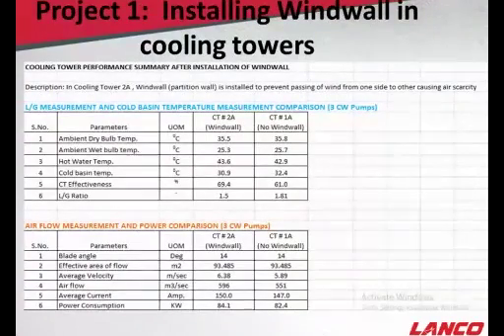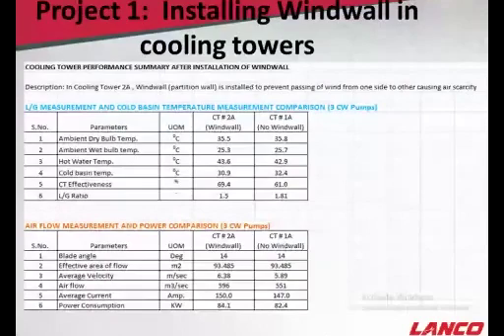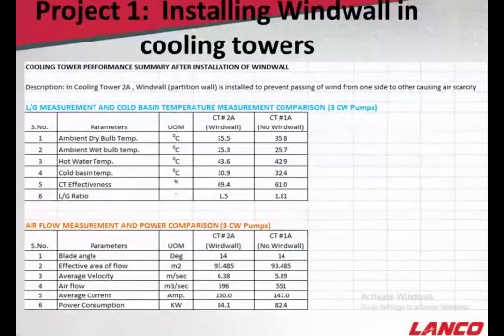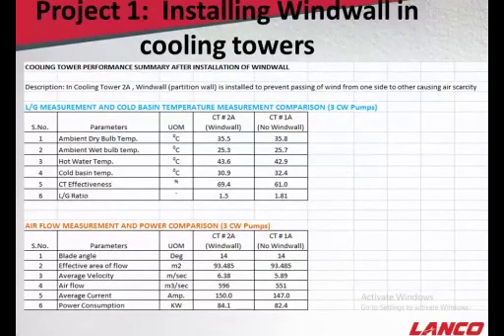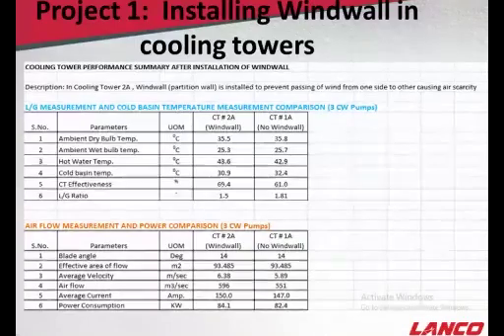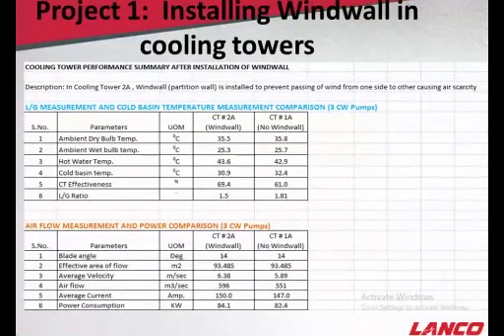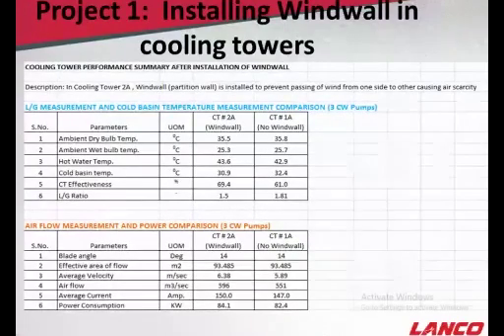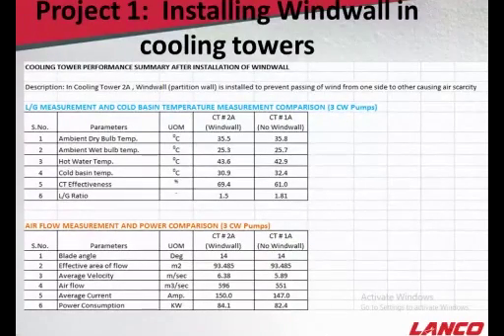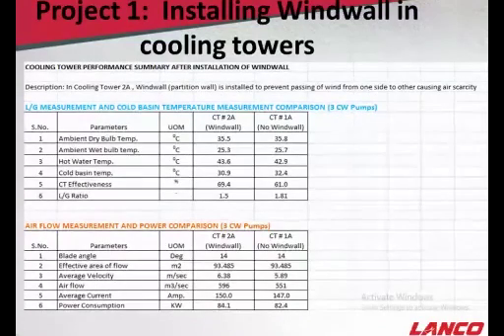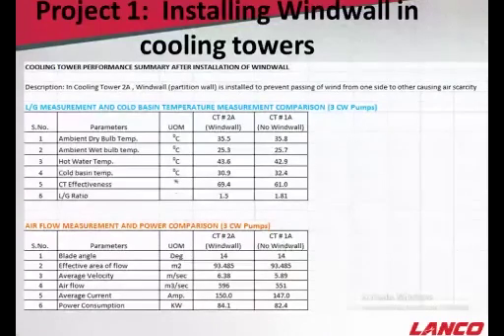If you see, these were the readings taken for different CT fans before wind wall and after wind wall installation. You will find 2-3 important points. L/G ratio was reduced. The CT effectiveness was increased, and the cold basin temperature was down. So these 3 things were very important. And actually, we came to know when first it was in the summer season, after running all the CT fans, we were not able to get the CW inlet temperature. So these are the results that we know.